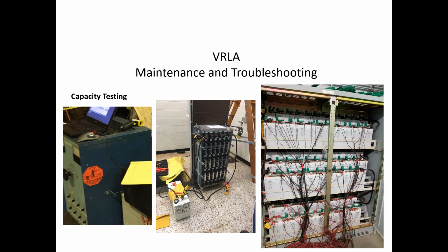typically designed around the application. So a switchgear battery is usually designed for high rate short discharge. Batteries of that nature are load tested anywhere from the 15 to 60 minute rate. The manufacturer publishes the rate: this battery can supply this much constant current for this period of time to this specific end voltage. And then we monitor the individual cells. Is that because the loads are such quick loads, like breaker closing and that kind of stuff? Yeah, exactly. You want to typically test that battery at a high rate because you're not only looking at battery capacity, you're looking at connection performance, you're looking at the whole thing. So you want to try to mimic the load as much as possible.